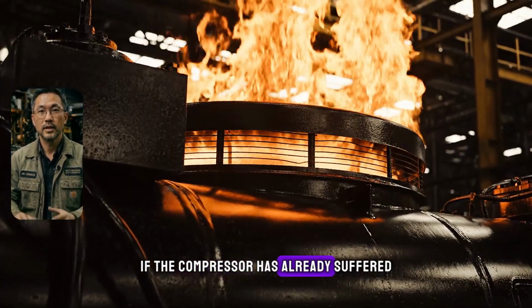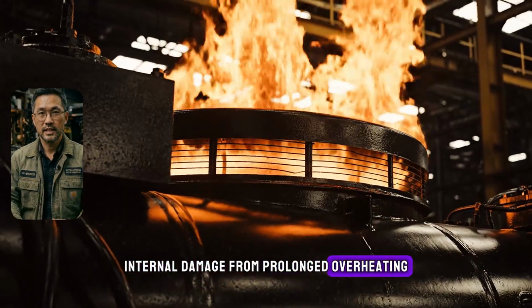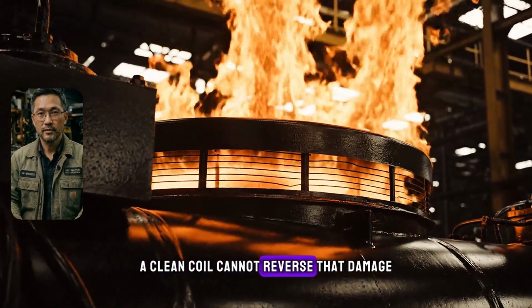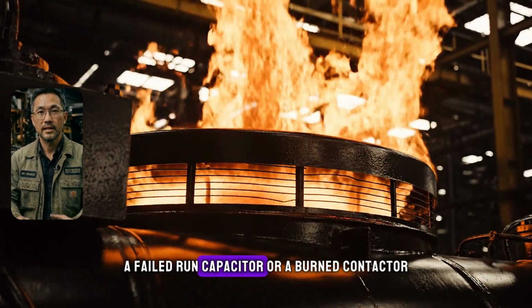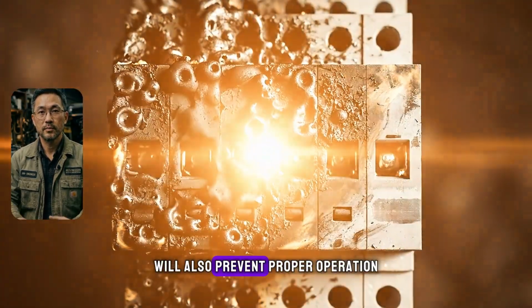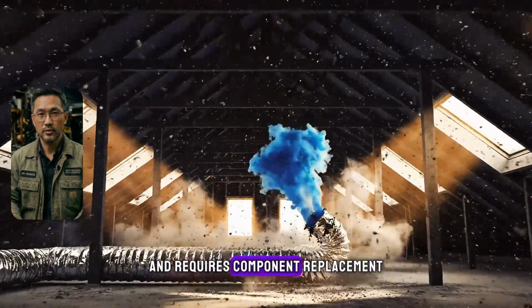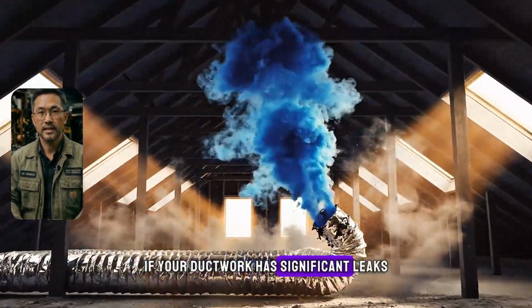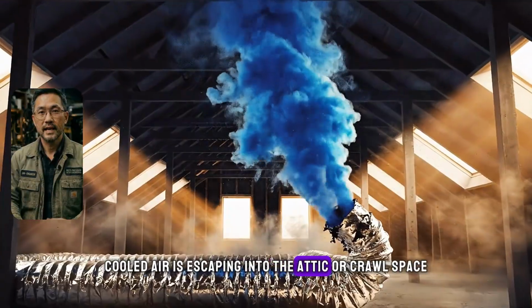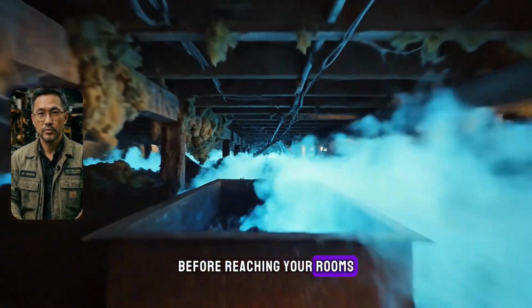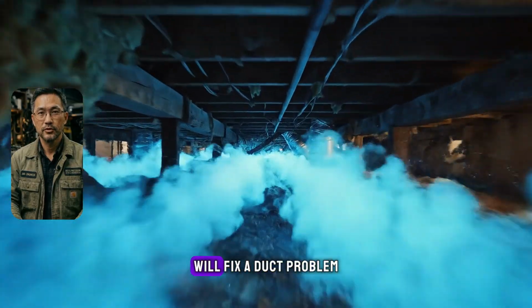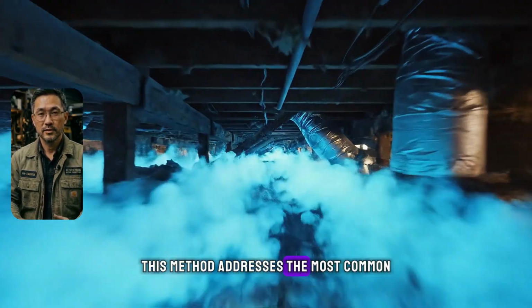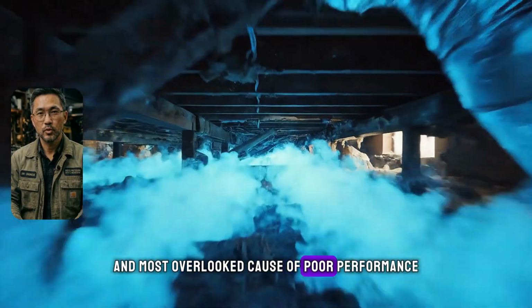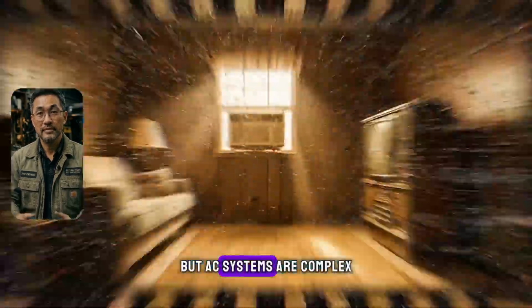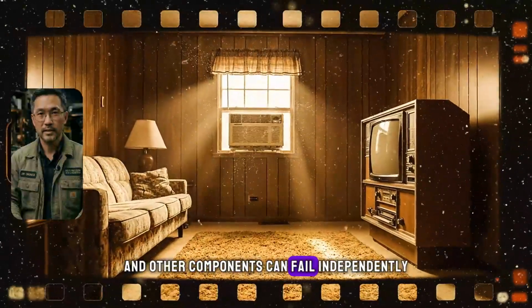If the compressor has already suffered internal damage from prolonged overheating, a clean coil cannot reverse that damage. A failed run capacitor or a burned contactor will also prevent proper operation and requires component replacement. If your ductwork has significant leaks, cooled air is escaping into the attic or crawl space before reaching your rooms, and no amount of condenser maintenance will fix a duct problem. This method addresses the most common and most overlooked cause of poor performance. But AC systems are complex and other components can fail independently.